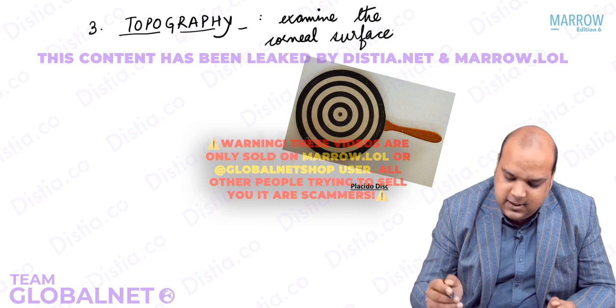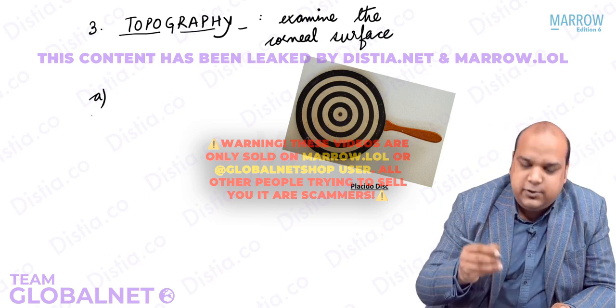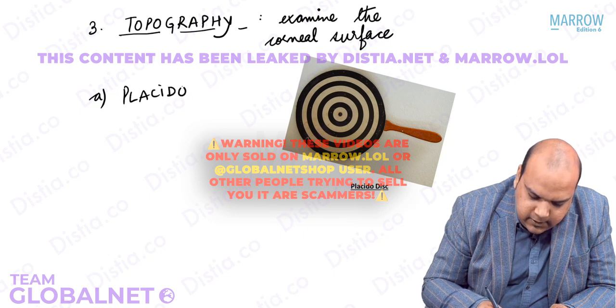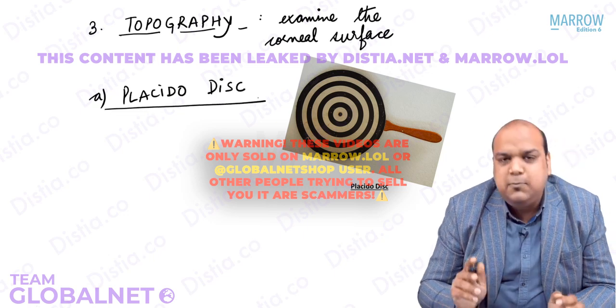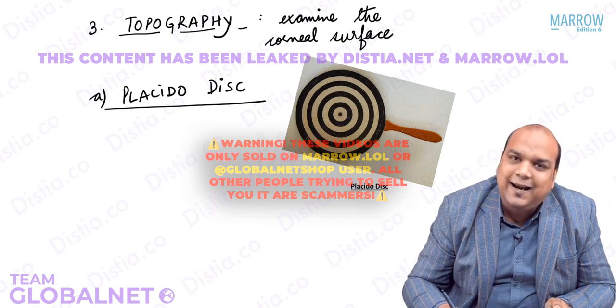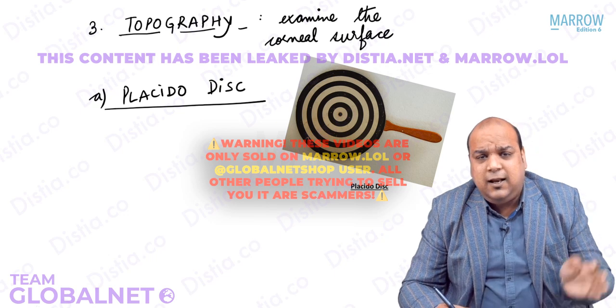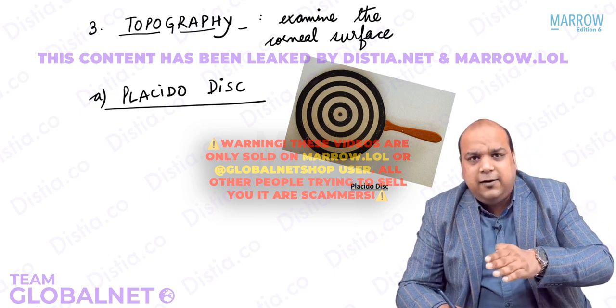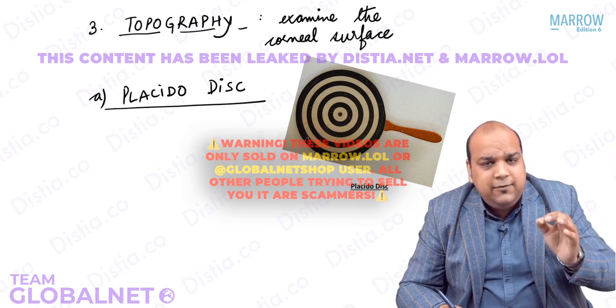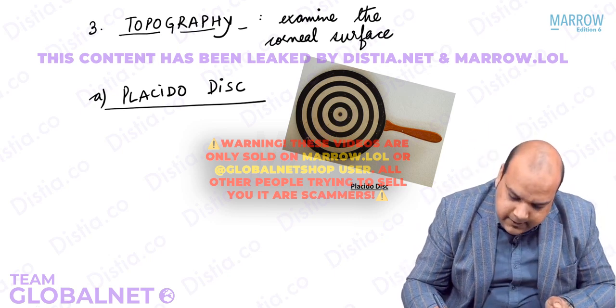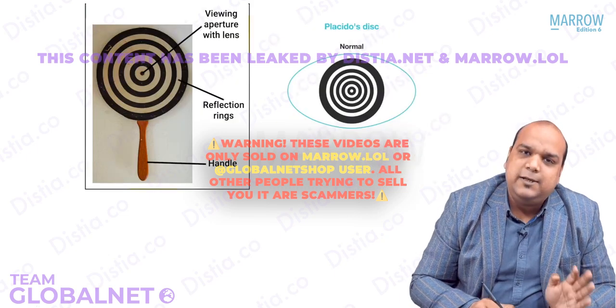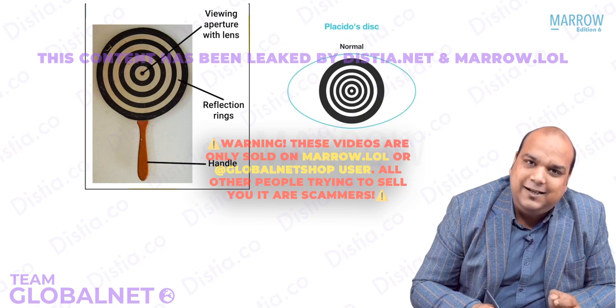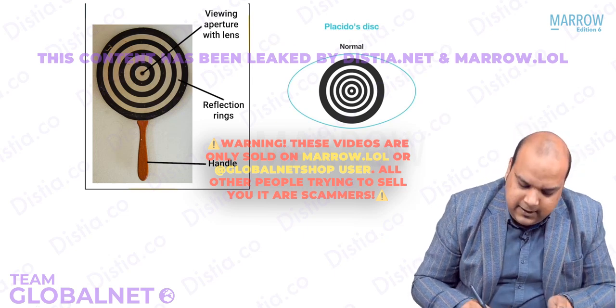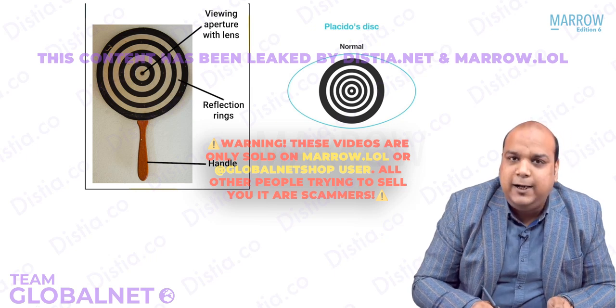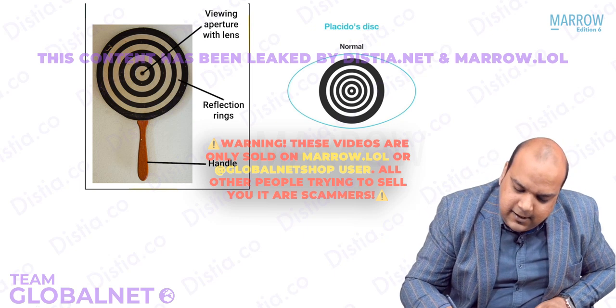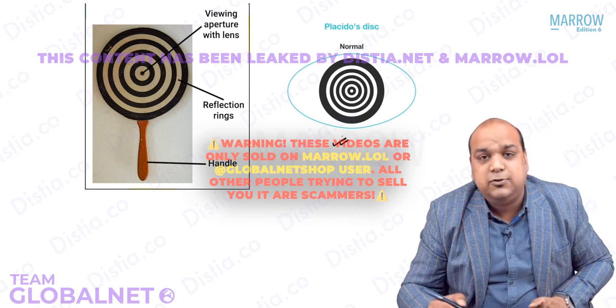Now, what are the instruments we use? First instrument, you will be able to see the image on the right side of your screen. This is called a Placido disc. This is the most basic instrument, consisting of dark and light colored alternating rings, as you can see in the image. A light is thrown on this Placido disc. This light reflects these rings onto the patient's cornea, and we are able to visualize these rings. Let's see how this is how a Placido disc works. This is a viewing aperture in the center with a lens. This is the handle which we are holding, and these are the rings of reflection. When we throw light on these rings, they reflect their image onto the patient's cornea, as you will be able to see in the image on the right side.